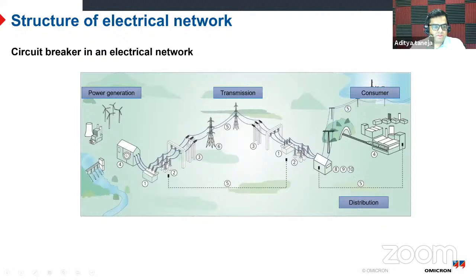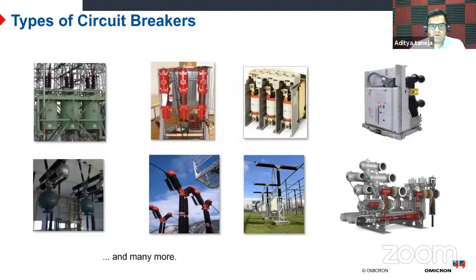But what we are going to focus on here are these two little black lines. These are circuit breakers, which are connected before and after the transmission line, or before and after any part of equipment, to operate whenever needed for maintenance or for clearing a fault. They are quite common in substations, and they are of various kinds. If I went into the different designs and technologies available for circuit breakers, I would need 2-3 hours just for listing them out.